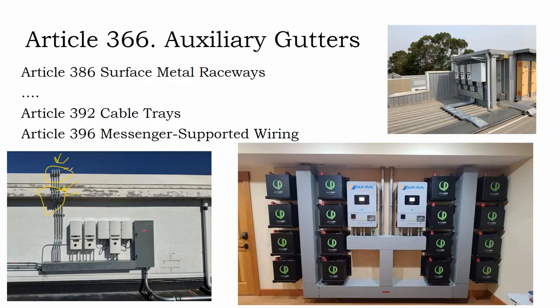What happened is the client came back out and said, well, we see your conduits looping off the side of the building and looping back down, and we're like, well, yeah, that's what's on the plans. And he said, well, okay, we did define it, but our vision was that this conduit hugs tight to the building. So we redid it to make it look better, and admittedly, it does look better, but also admittedly, cable tray should have been specified instead.